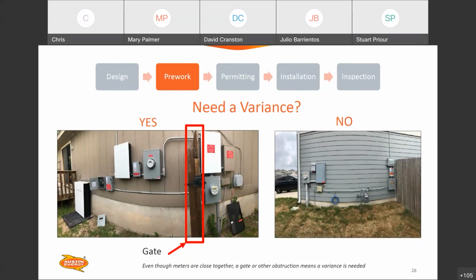But here's a good side-by-side of when you would need a variance and when you would not need a variance. Notice that those 2 meters on the left there, they're within 10 feet of each other, but you've got an obstruction between the two. So they're not technically in sight of each other. You've got a fence. So if you've got a building meter that you need to put behind a fence like that, that would be when you would contact Abdur at Austin Energy and get that approval before installing that meter. The picture on the right there, they've just separated the solar equipment from the main service to avoid the gas regulator there. That's within sight. It's as close as practical, and it's all on the same wall with no obstruction. So you wouldn't need a meter variance in that case.